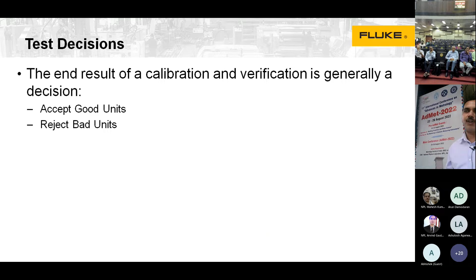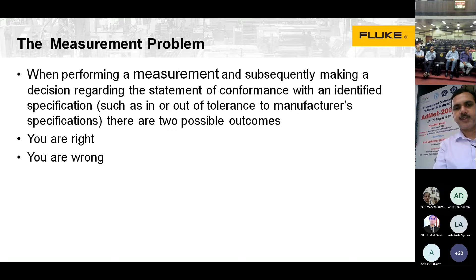The end result of a calibration and verification is generally a decision, to accept good units or to reject bad units. Now, when performing a measurement and subsequently making a decision regarding the statement of conformance with an identified specification, such as in or out of tolerance to a manufacturer's specification, there are two possible outcomes: you are right or you are wrong.